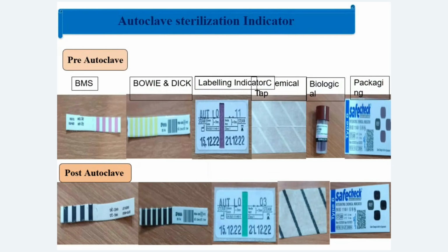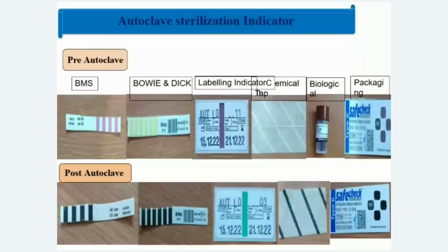You'll be using chemical indicators, biological indicators, and Bowie-Dick. At the beginning of each day, you need to use a Bowie-Dick for any air leak. And the color changes. The staff have to be trained. Staff, including doctors, have to be trained by the CSSD team how the chemical indicator looks like before sterilization and post sterilization, how the color changes, so that when these indicators are put inside the sets and these sets are opened in the OT only, if the color has not changed, they should not be using the sets and they have to be returning it to the CSSD for re-sterilization.